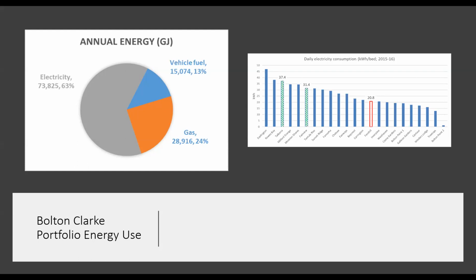Looking at a range of Bolton Clarke facilities, the graph on the right shows kilowatt hours per bed across a range of facilities. Notice the variance, between a low of around 15 kilowatt hours a day and a high of about three times that. So just looking at kilowatt hours per day is not enough to determine whether a facility is being energy efficient and optimised.